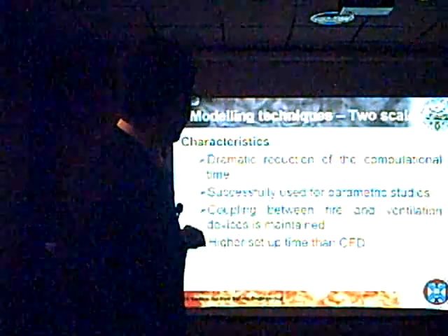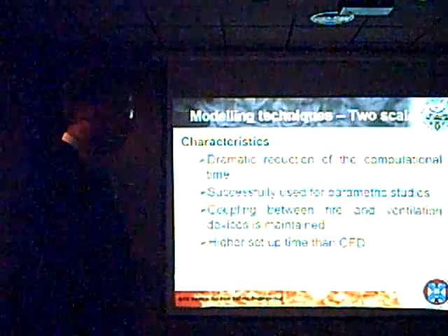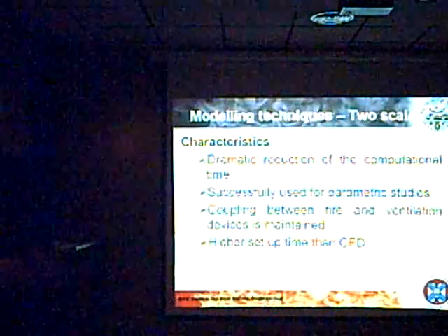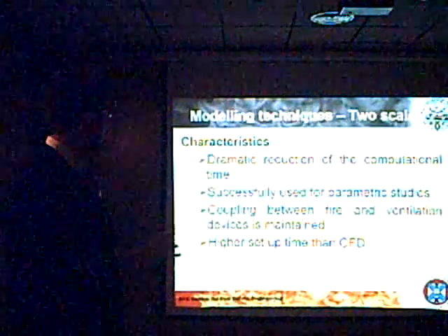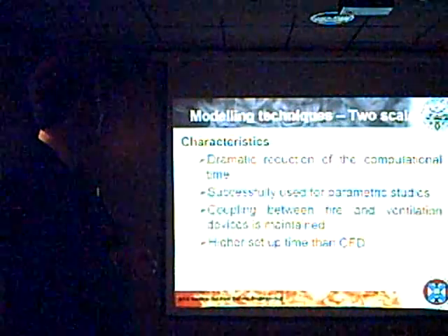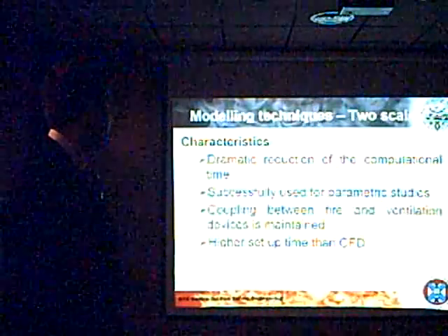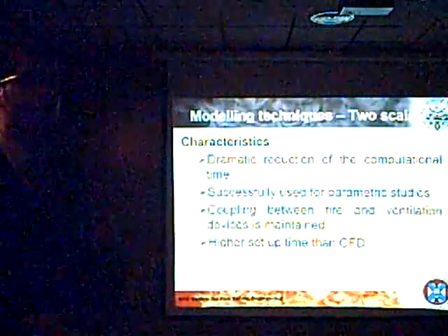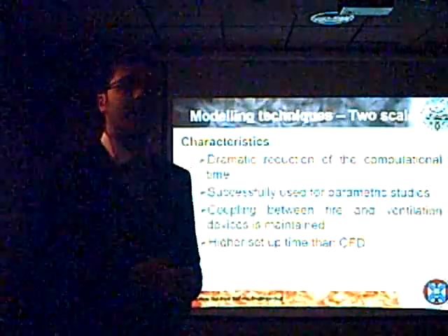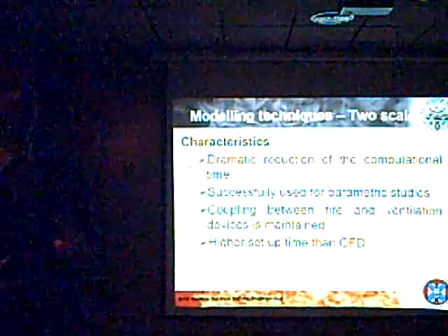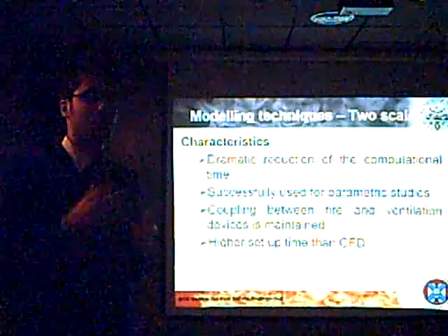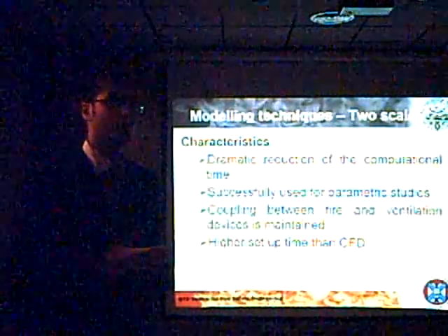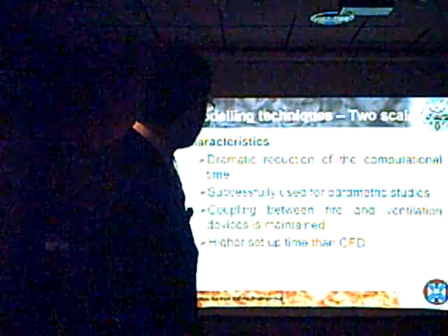So, at the end, the computational time is much lower. This kind of model can be successfully used for parametric studies, and obviously the setup time, the time we need to build the curve, is higher. But we can try to use them to understand if a fire with this size, dimension, and location can affect the final ventilation condition within our tunnel.